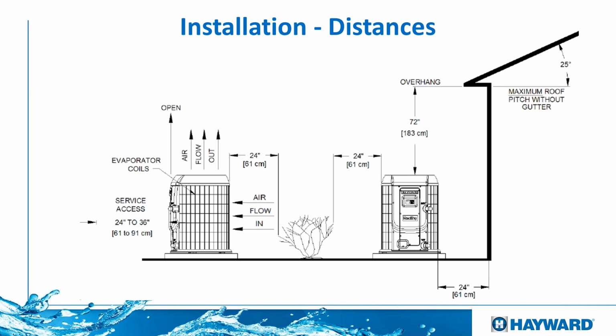It gets to a point where the air around it is going to have no more heat. So by placing them outdoors, you're going to get the best out of them. Also, please keep in mind that we have to have some kind of distances. As you can see in this picture, you'll see this, by the way, in the installation manual. It has to have some kind of clearance between a ceiling, a wall, or a plant, or something that is obstructing it, so it can better work. It can breathe better. So keep that in mind, please.